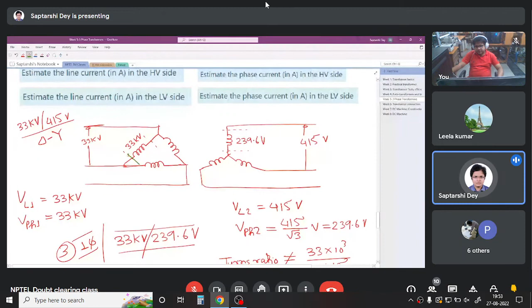So when I have 33 kV applied in this winding, I am getting 239 volt induced in this secondary. That means if I count the number of turns here and here and make a ratio, I will get this 33 kV by 239. The turns ratio is at the transformer level. Say for example, this transformer. Okay, got it.